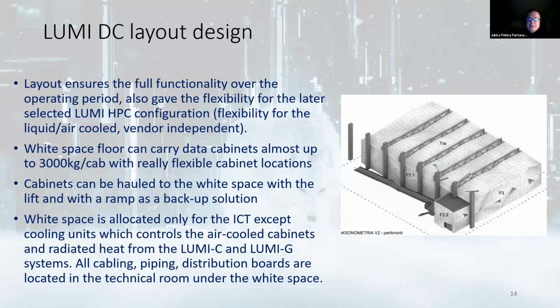And white space is allocated only for the ICT, except the cooling units, which control the air-cooled cabinets and radiated heat from the Lumi C and Lumi G systems. And all cabling, piping, and distribution boards are allocated in the technical room under the white space. So we take electricity and cooling to cabinets from the bottom.